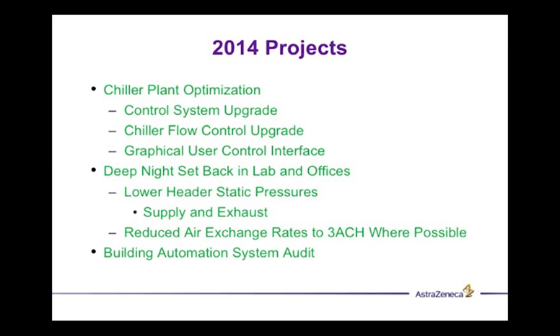So we run about 2.1 inches of static pressure all day, okay? Because we need that for volumetric to get the fume hoods to work. So then we go into night setback, which we had done a few years before that. And we found we can go to 1.5 inches of static pressure. There's not that many people left, right? So you work on diversity.